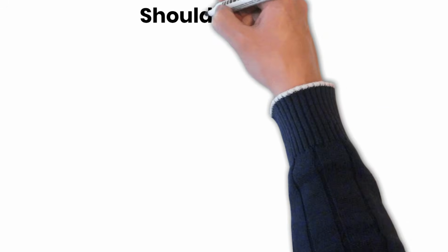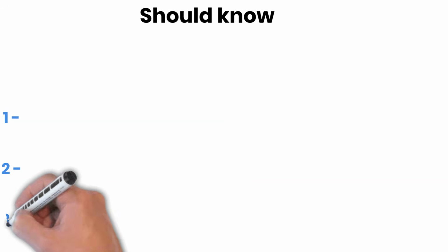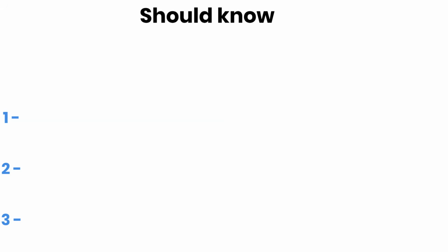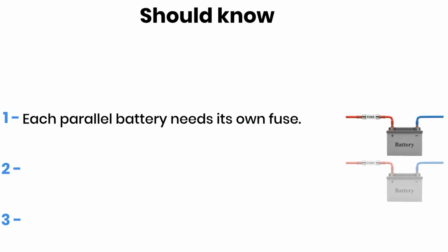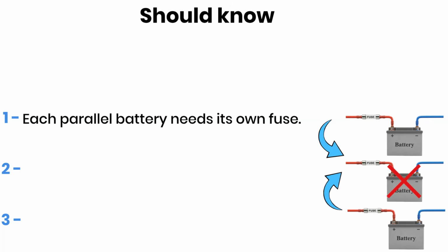Before we compare the different layouts, there are three important things you should know. The first one is that every battery connected in parallel should have its own fuse. Here's why this matters. If one battery develops an internal short circuit or another serious fault, the remaining batteries can instantly feed a huge amount of current into that failed battery. Without individual fuses, that fault current can become extremely dangerous and may damage cables, battery terminals, or even start a fire. Adding a fuse to each battery helps isolate a fault before it can affect the rest of the battery bank. It's one of the simplest safety upgrades you can make.